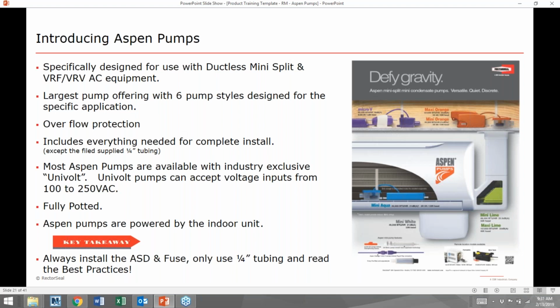One of the big takeaways from today is that most Aspen pumps are available with the industry-exclusive Univolt. Univolt pumps can accept voltage inputs from 100 to 250 and everywhere in between. The board will self-modulate, so as there might be dips or spikes in the voltage, the pump controls will manage that, and the pump will deliver consistent performance.